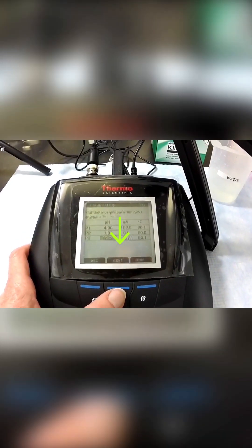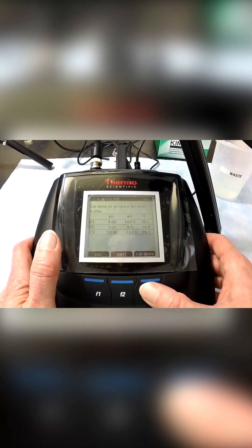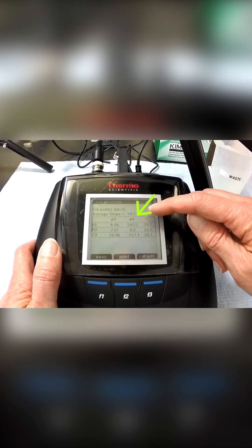To complete the three-point calibration, press accept, then CAL done. The average slope will be displayed here at the top.